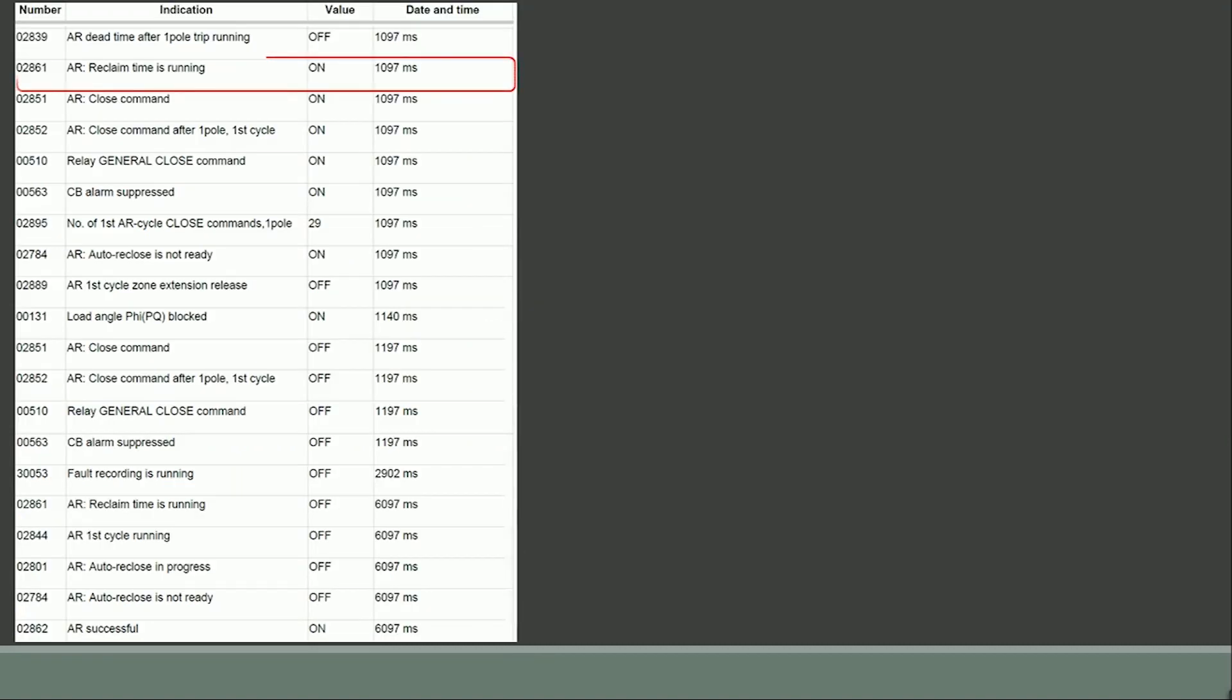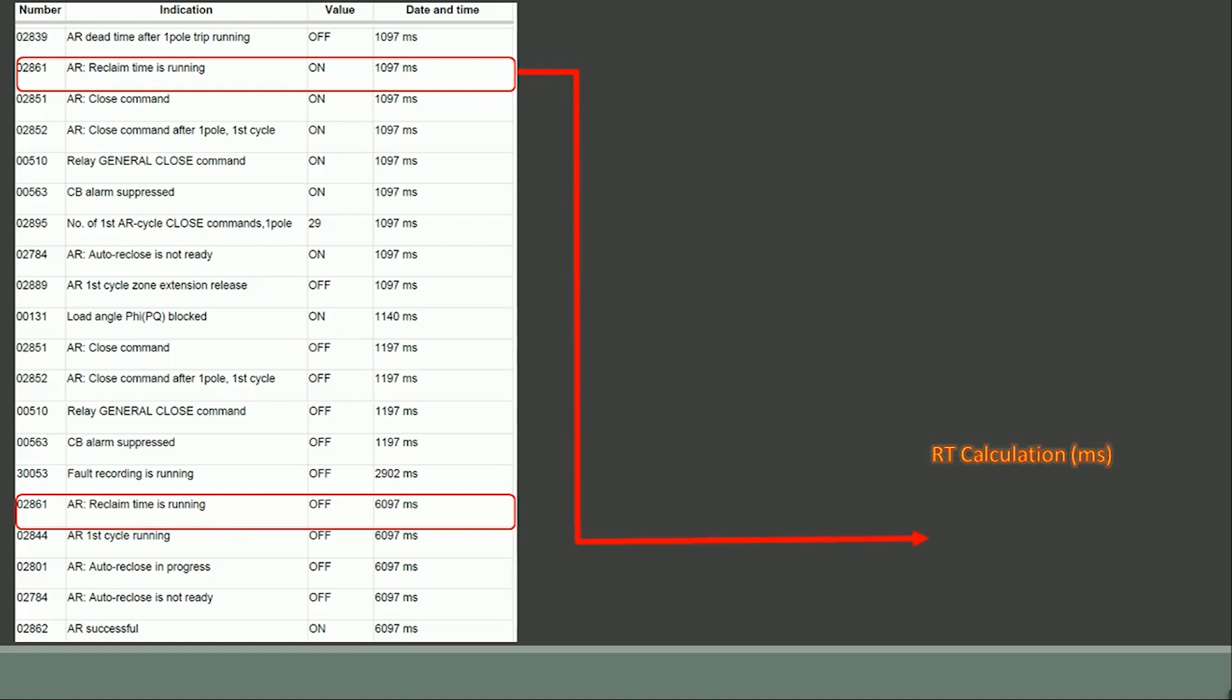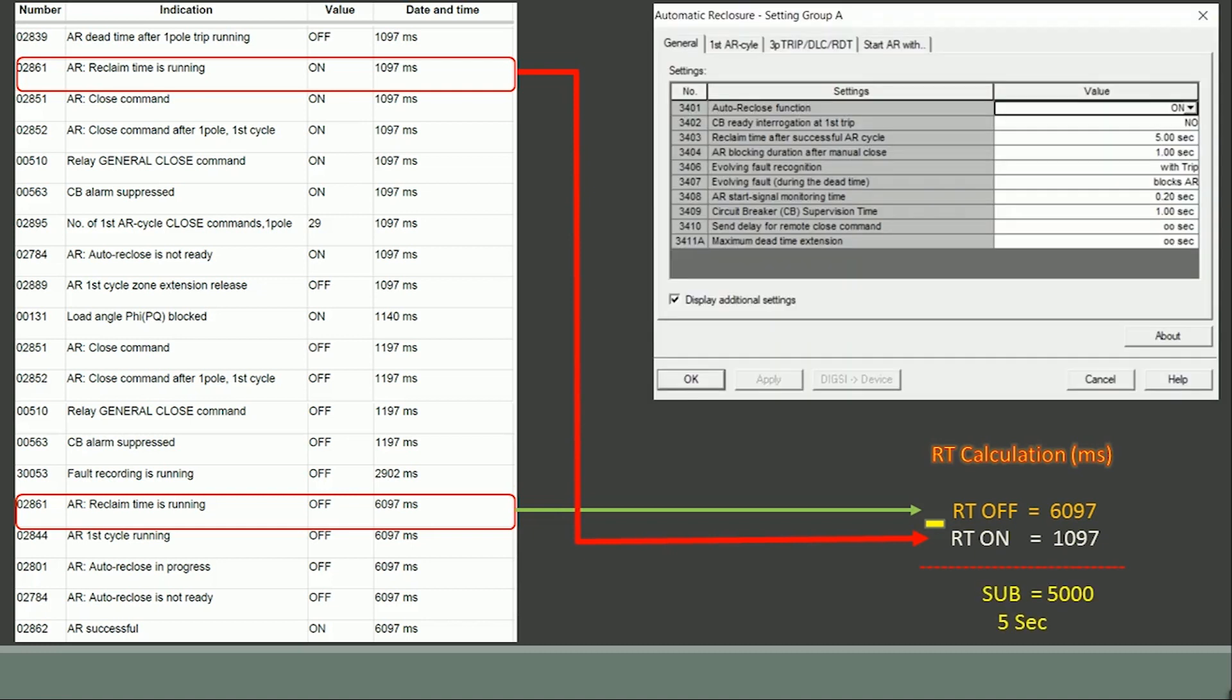The auto reclose reclaim time is started at 1097 milliseconds as per parameter number 02861 and it's turned off at 6097 milliseconds as highlighted. The difference between reclaim time off and the on time provides the reclaim time configured in the relay as 5 seconds as per setting parameter number 3403.